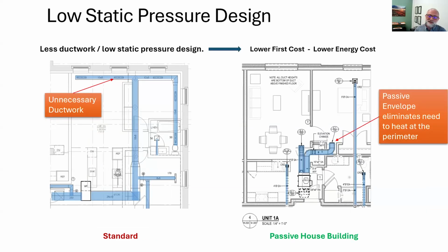So another important design principle is low static pressure design for ductwork and equipment, and minimizing the ductwork in the systems. Residential HVAC systems and commercial HVAC systems typically supply conditioned air at the perimeter wall near the windows. In fact, some housing authorities mandate this approach because typically double pane windows are uncomfortable when it's really cold in the wintertime. So the approach is to wash those windows with conditioned air. But the passive building insulation creates a comfortable environment without the need to wash the windows with conditioned air. So to take advantage of this, the system should be simplified and minimized to reduce fan energy and first cost in the system.